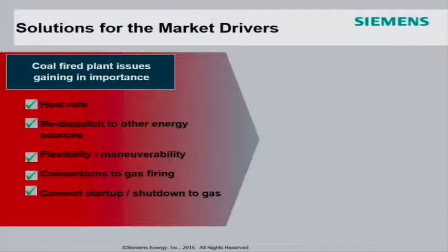So fundamentally, when we looked at what they were facing, we were looking at hard stops. We were looking at the flue gas temperature minimum for the scrubbers and equipment on the back end. We're looking at vibration on the turbine. So there are hard stops to minimum load reduction. We can do a lot with controls, increased stability, things like that, but those hard stops require significant investment. So between the head office and the plants themselves, there seems to be a slight discrepancy about what is achievable and what can be done. And also we're seeing that the incentive side of this whole issue seems to be lacking a little bit, but I'm sure as we go forward, we'll see more incentives.